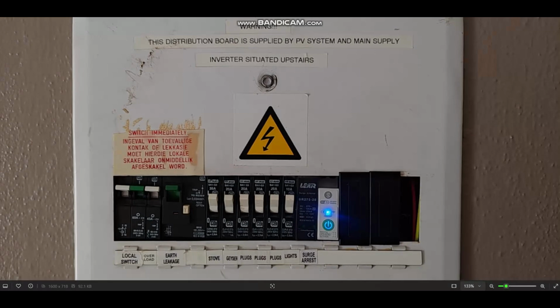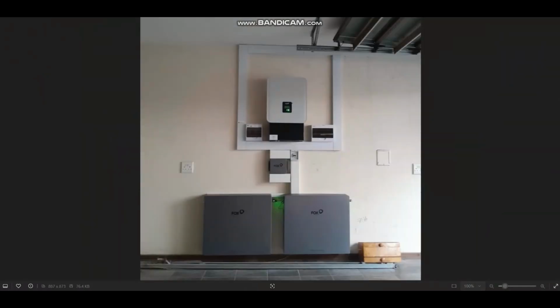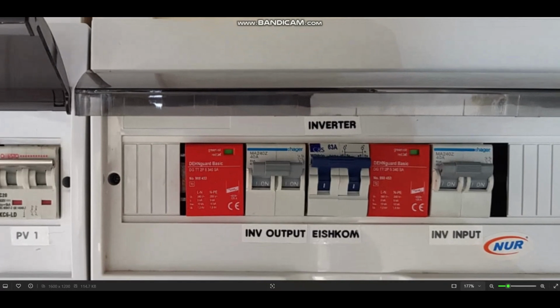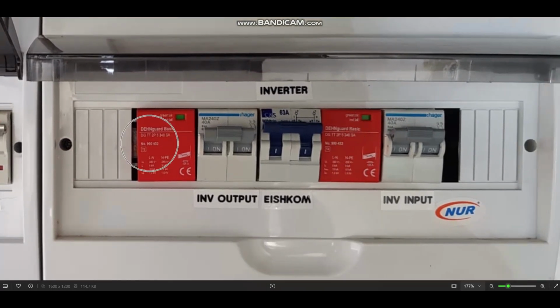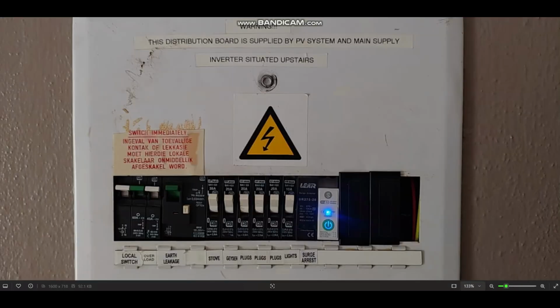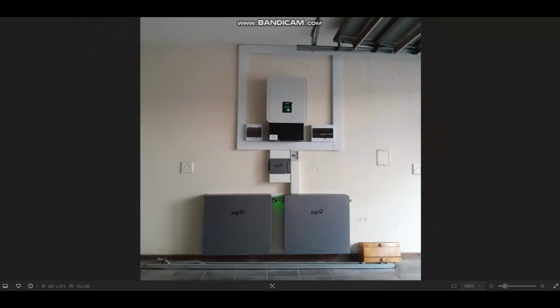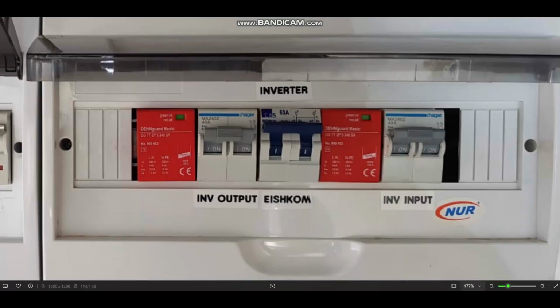The second layer of surge protection is what we call an AC distribution board. There it is over there. And if we open that little flap, this is what it looks like. So you'll notice another 2 orange surge protectors, one for the input to the inverter, and that is the supply channel from your main distribution board to your inverter. It needs to go through this gatekeeper over here.